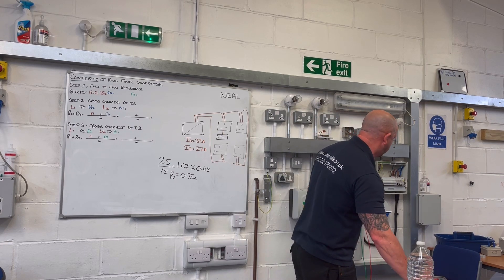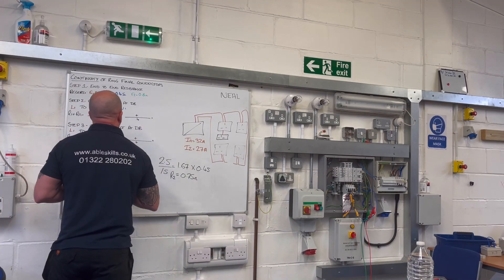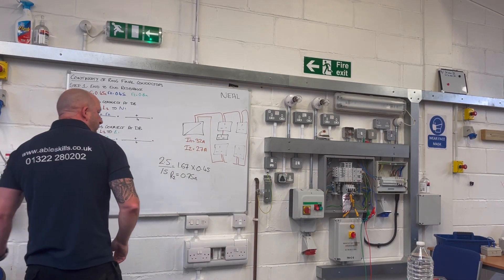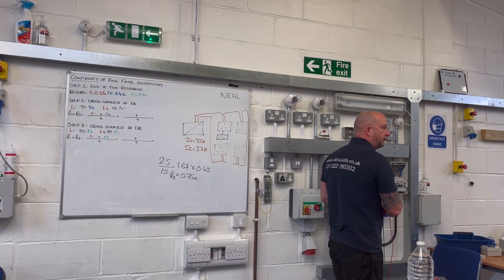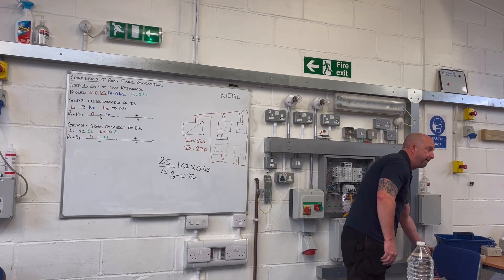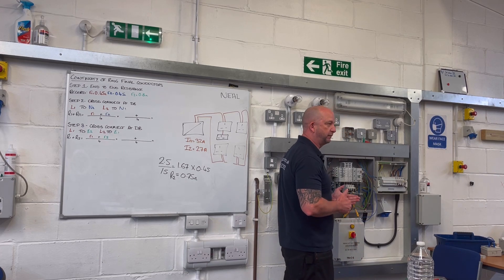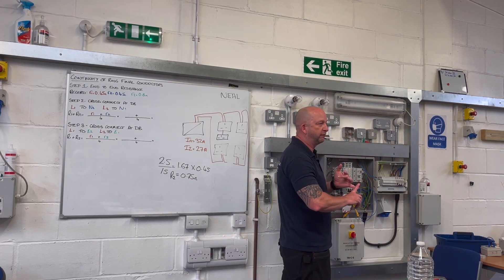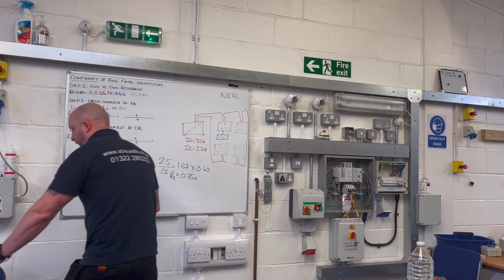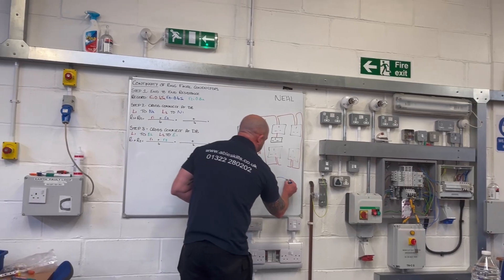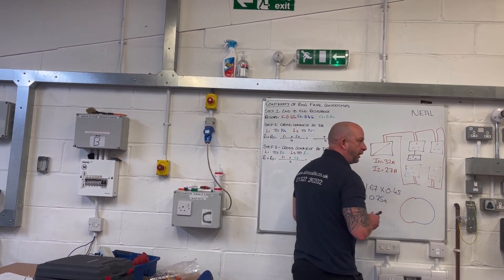So that's step one in the bag, guys. Any questions? Moving on to step two then. What's step two? We need to make a cross connection at the distribution board from one leg of the ring to the other. Effectively, we're turning our cables into one big loop of cable — we're going to connect our neutral to our line. That's what we're going to do.